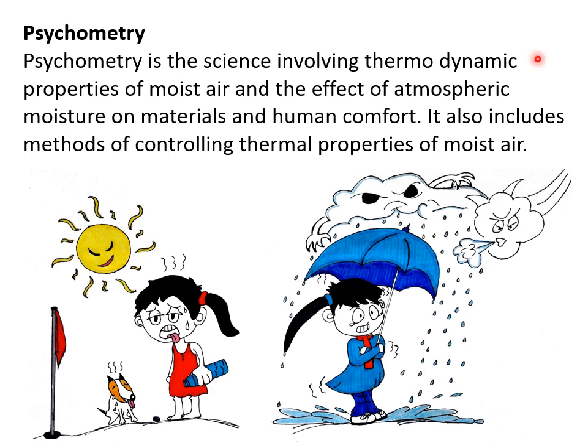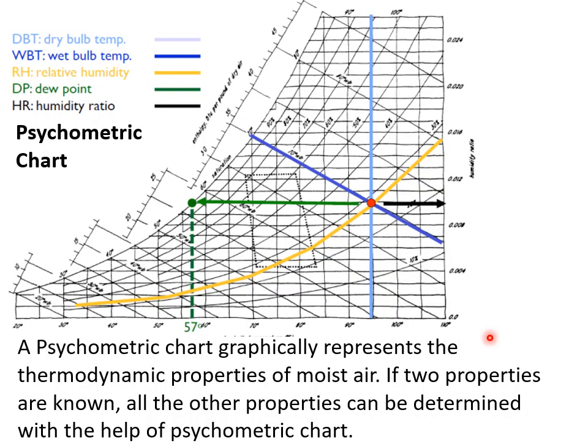Psychrometry is the science involving thermodynamic properties of moist air and the effect of atmospheric moisture on materials and human comfort. A psychrometric chart is a graphical representation of the thermodynamic properties of moist air. If two properties are known, all other properties can be determined. At the x-axis we indicate dry bulb temperature, at the y-axis relative humidity, and the curvilinear line indicates the wet bulb temperature. We use this psychrometric chart in the design of HVAC systems.